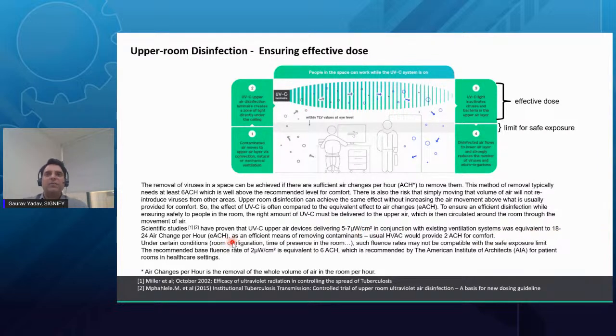So now the question comes, why can't we just improve the air changes, and that is how we improve the indoor air quality? But there are certain risks with that, because if you change the air continuously in the indoor environment, that infectious air can go from one area to another area. So you need to find a way to disinfect that air. That is why an upper room UVGI system should be in place.